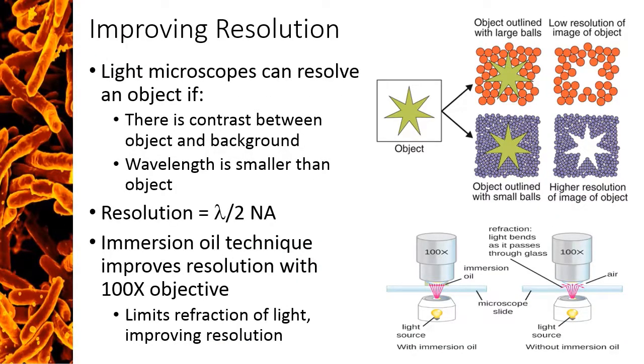Light microscopes are able to resolve objects as long as there is contrast between the object and the background, and the wavelength of light is small enough to pass by the object. The resolution of a light microscope can be calculated by the equation lambda, which is the wavelength, divided by 2 times the numerical aperture. The numerical aperture is a property of the quality of the lens itself, and cannot be changed. So the only variable in this equation is the wavelength of light. The smaller the wavelength, the smaller the resolution, which means the better the resolving power. This is highlighted in the image with the circles and the star.